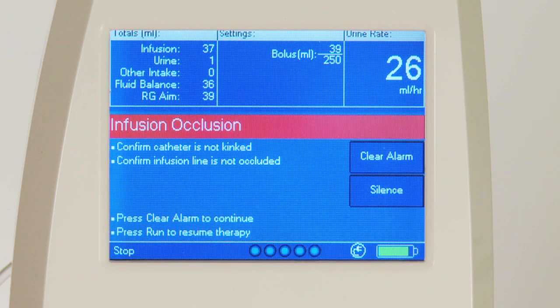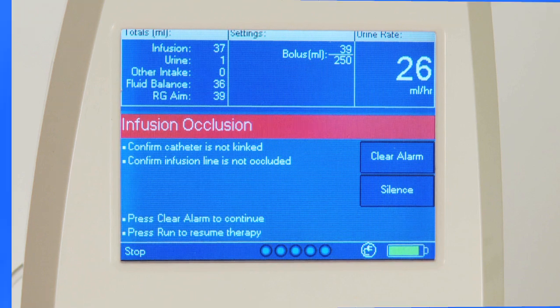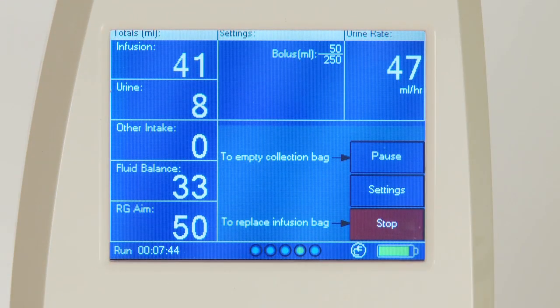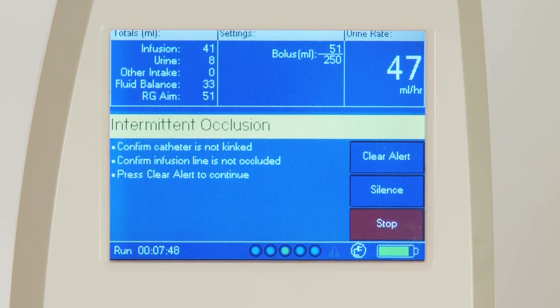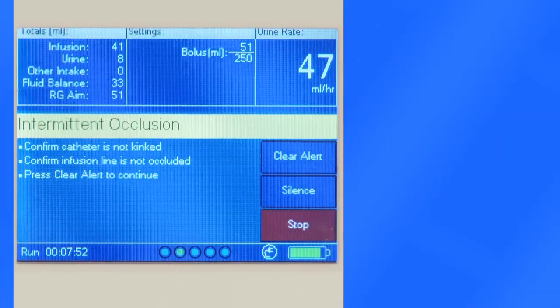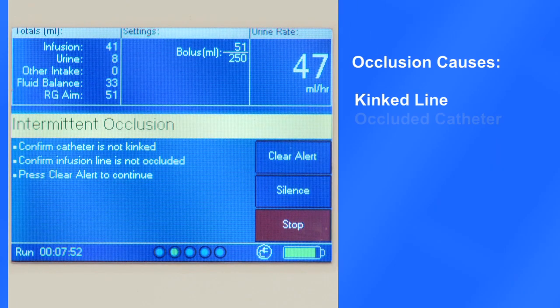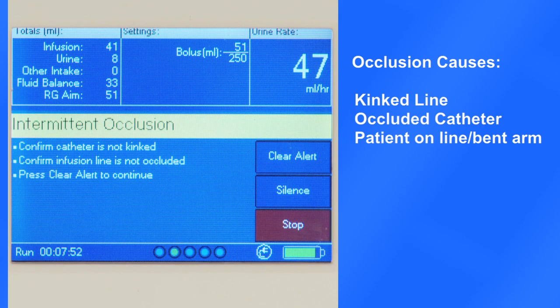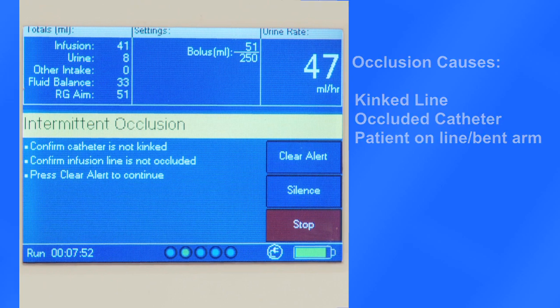Full occlusion: if the console detects a full occlusion, the pump is stopped and the infusion occlusion alarm is displayed. Intermittent occlusion: if the console detects an occlusion that comes and goes, the pump continues but the intermittent occlusion alert is displayed. Potential causes of occlusion are a kinked line, an occluded catheter, the patient is resting on the line, or the patient's arm is bent.